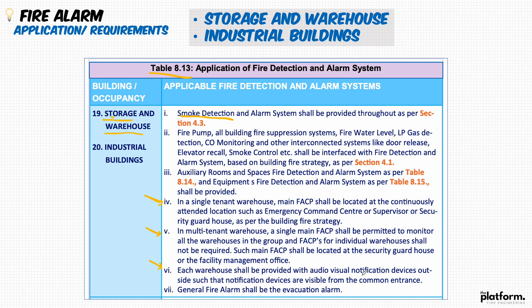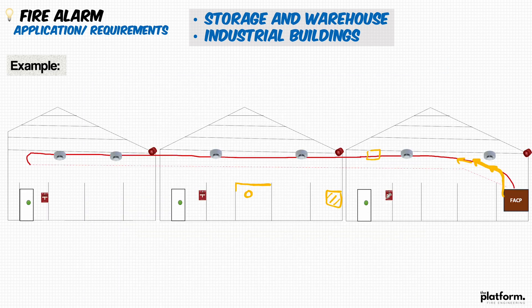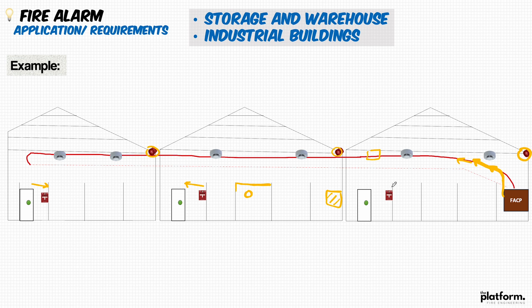Each warehouse shall be provided with audio-visual notification devices outside, visible from the common entrance. The number of devices will be based on the distances and the design of the area. In addition, a manual call point should be added near each exit, within a distance not more than 1.5 meters, as we learned from previous lectures. The design and selection of the fire alarm system is as simple as going through the code, understanding the requirement for each occupancy, and applying what you've learned about device distances and selection.